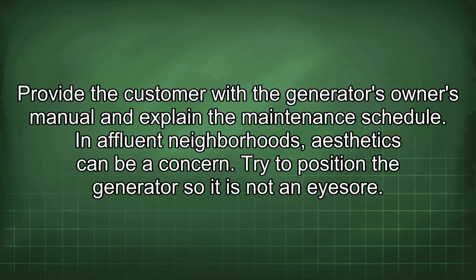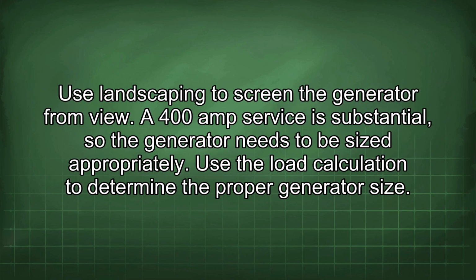In affluent neighborhoods, aesthetics can be a concern. Try to position the generator so it is not an eyesore. Use landscaping to screen the generator from view. A 400 amp service is substantial, so the generator needs to be sized appropriately. Use the load calculation to determine the proper generator size.